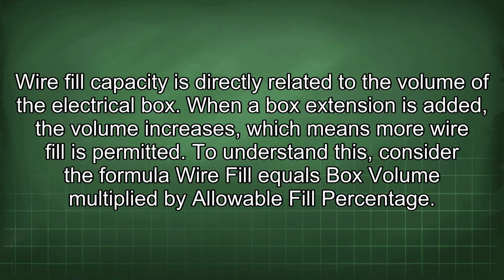Wire fill capacity is directly related to the volume of the electrical box. When a box extension is added, the volume increases, which means more wire fill is permitted. To understand this, consider the formula: wire fill equals box volume multiplied by allowable fill percentage.